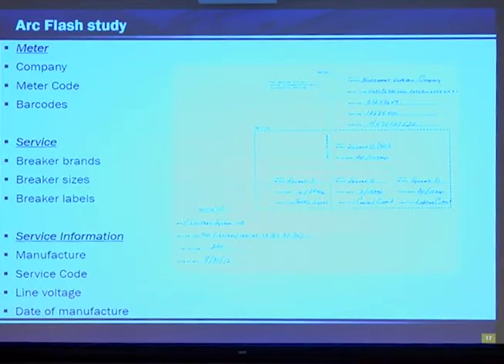Number two, we need to know how many pole amps that circuit breaker is. And lastly, number three, we need to know what type of load that circuit breaker is feeding. Looking at the service information block, we need the manufacturer, service code, line voltage, date of manufacture. All that service information can be found on a label inside the panel.